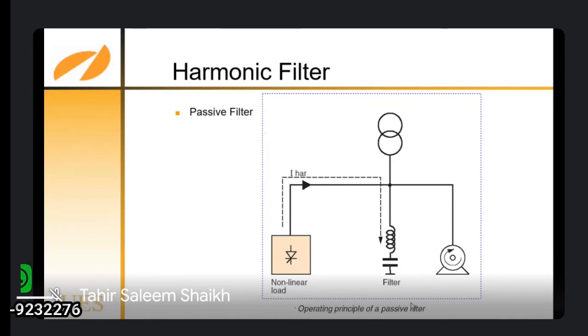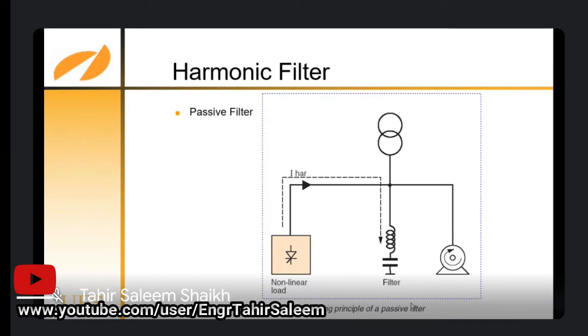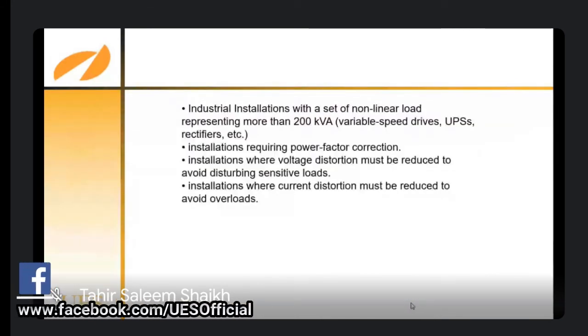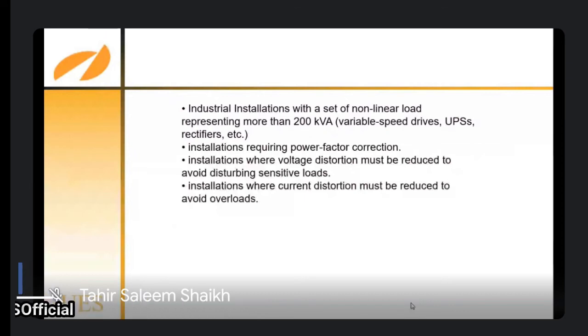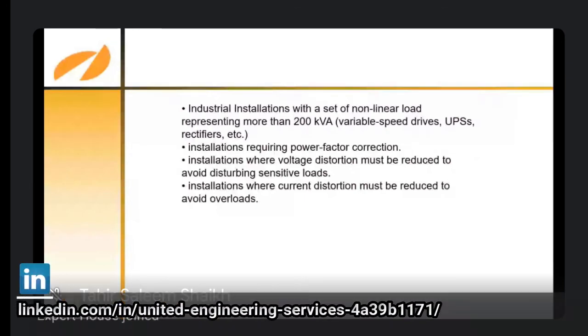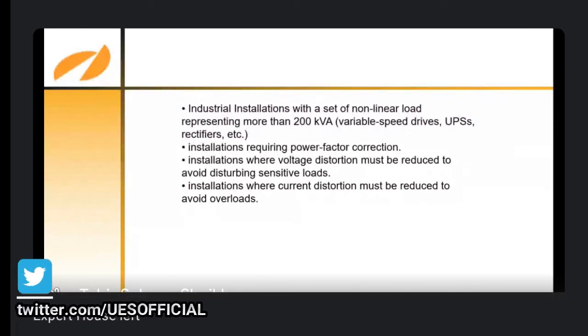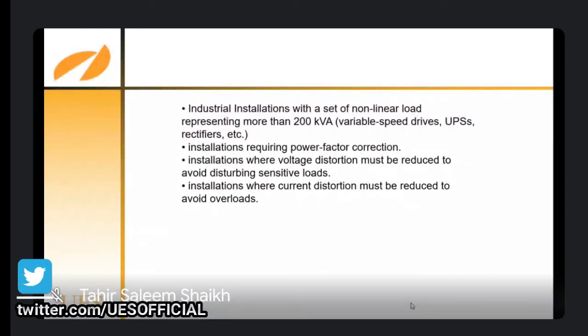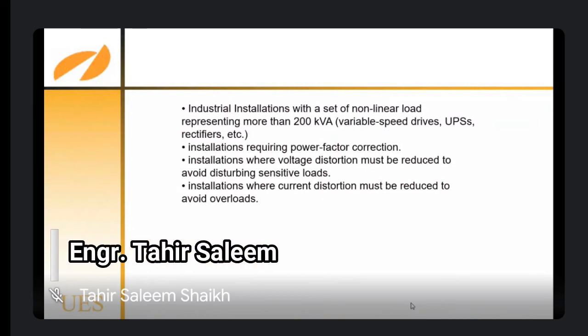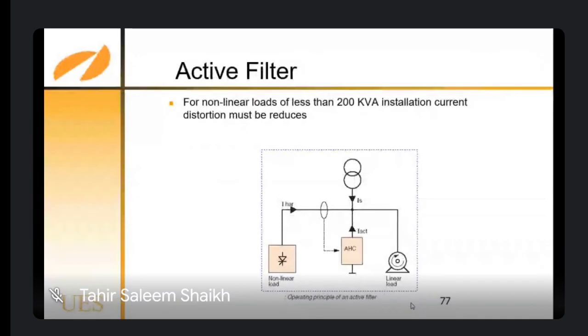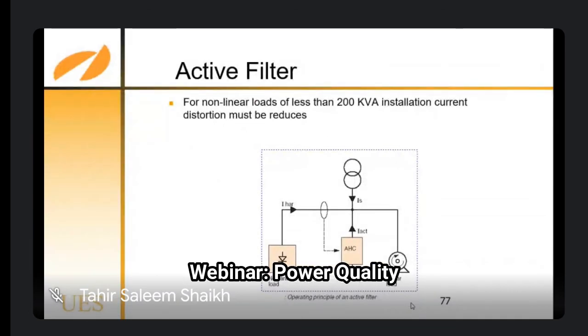Normally it is used in industrial installations with a set of non-linear loads representing more than 200 kVA, UPS installations requiring power factor correction, installations where voltage distortion must be reduced to avoid disturbing sensitive loads, and installations where current distortion must be reduced to avoid overloads. Now, this is also very expensive.